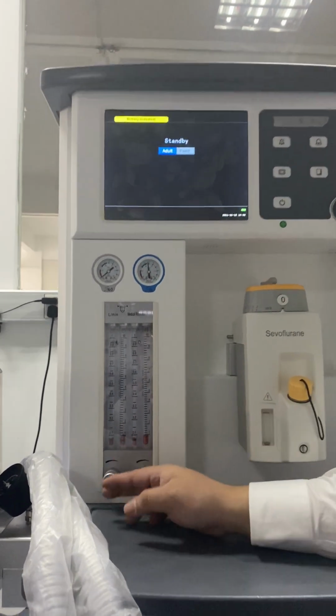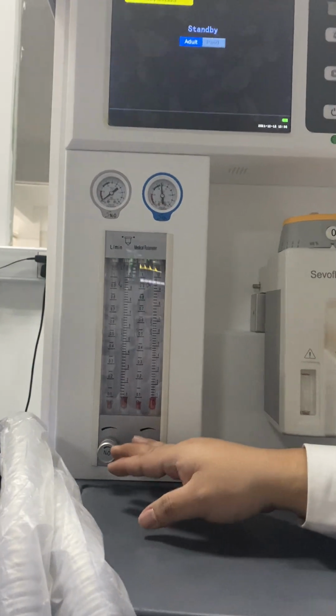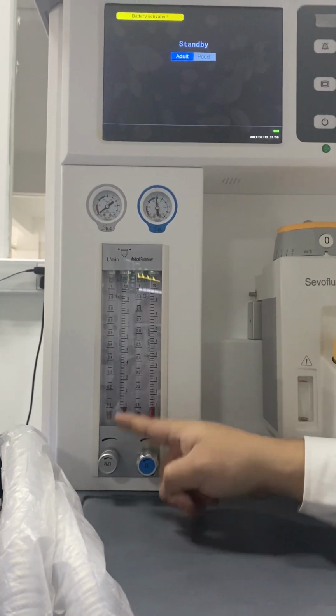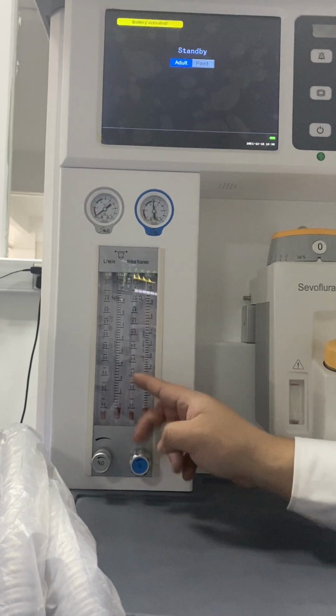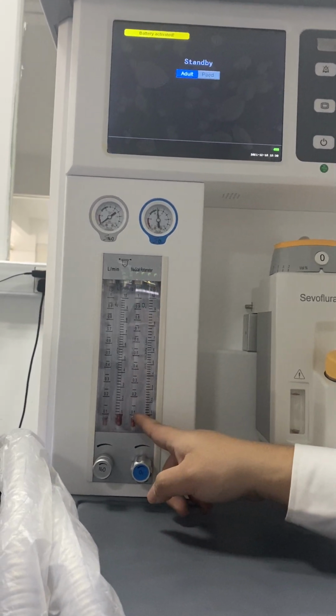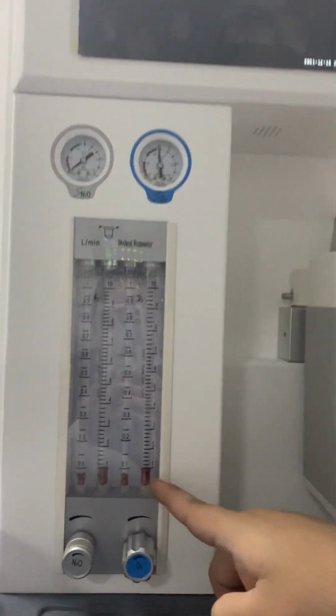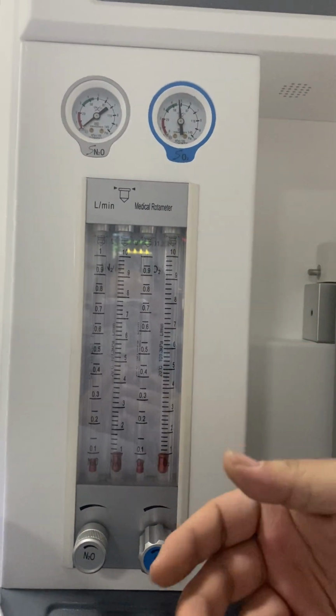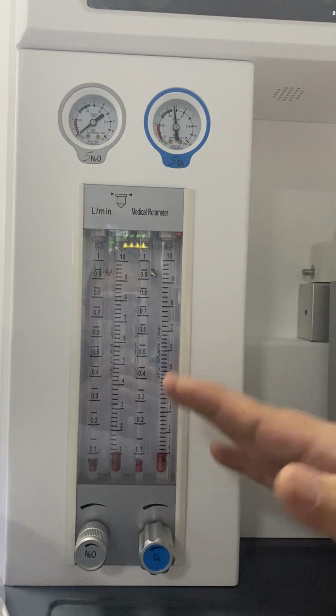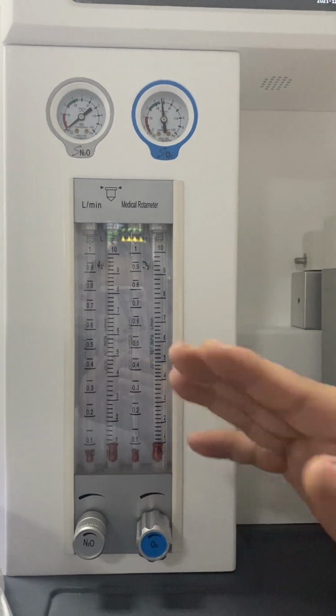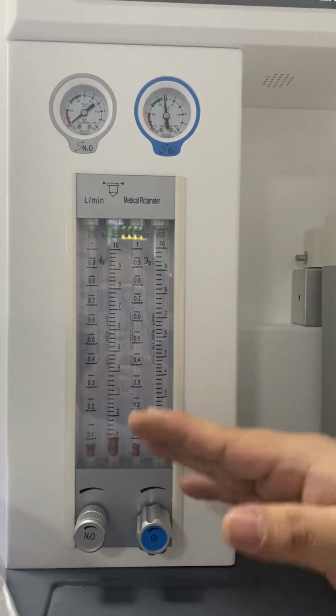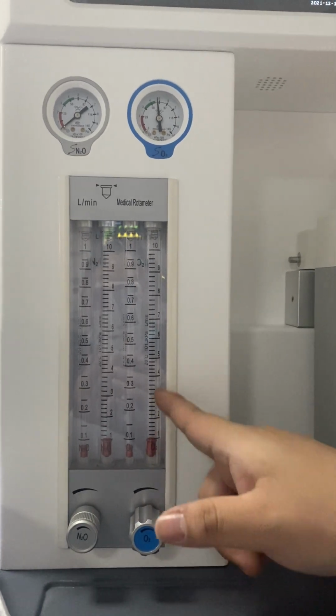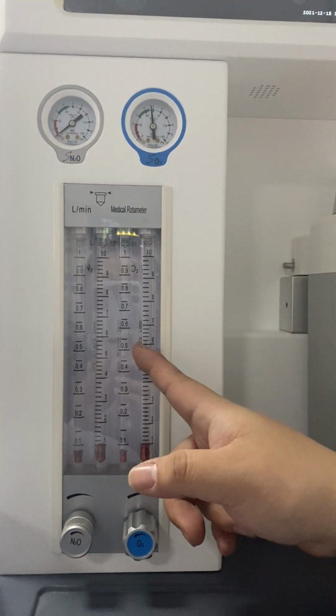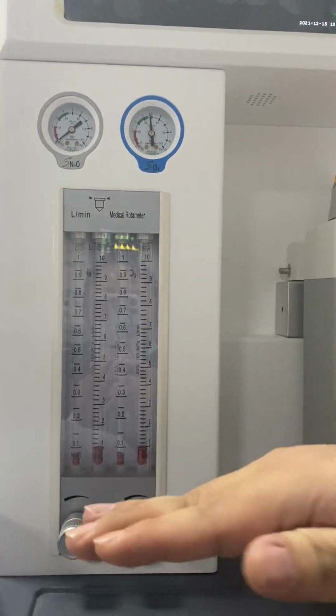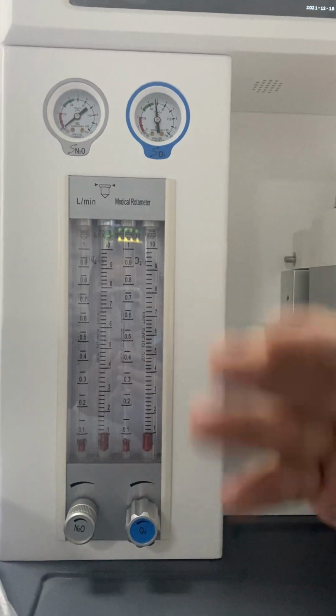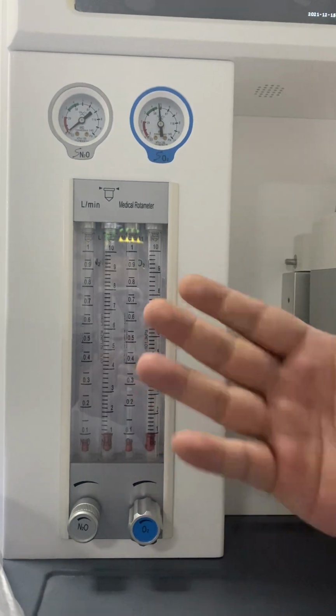The flow meter is the same. Because it's a 2-gas system, it has 2 flow meters, one for each of the gases. But you can see the 2 flow meters, one is from 0.1 to 1, and another one is from 1 to 10. We have this design because we want the setting on the mechanical flow meter to be accurate enough. For example, if we are setting about 6.5, then from this line it will be 6, and from this line it will be 0.5. So it will be directly what you have just set, and there is no need to check it again and again to keep the accuracy.